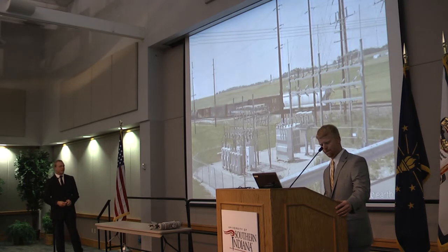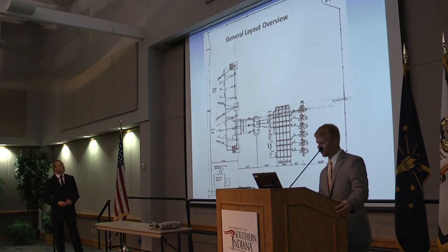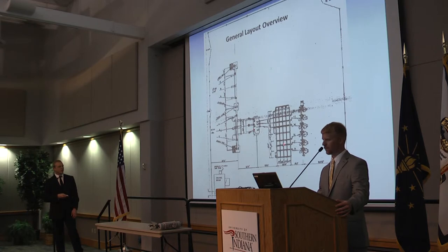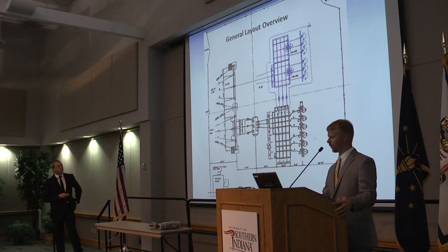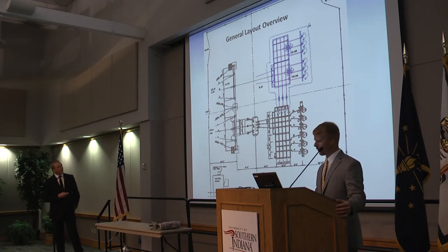This is another close-up of the substation, just to give you an idea. From here, we made our general layout. This is the existing. 69 comes in here. This is the transformer. It goes into the regulators in the bus, or the breakers in the bus, and it gets regulated and goes out. So what we're going to do is attach new bus to here, and we're only dealing with the third exit for now, but we designed it for the fourth, and the transformer will be here. It'll be connected, and this is the circuit breaker, this is the bus, and it'll be regulated and attached to the distribution exit.